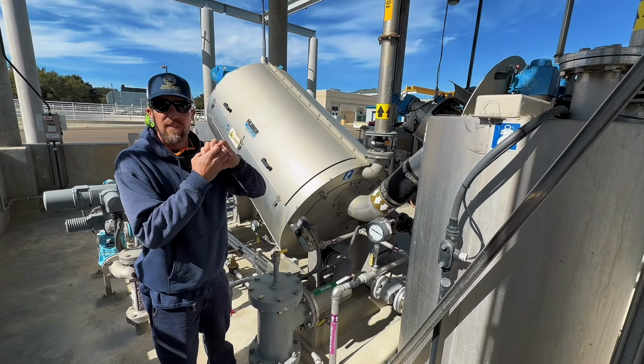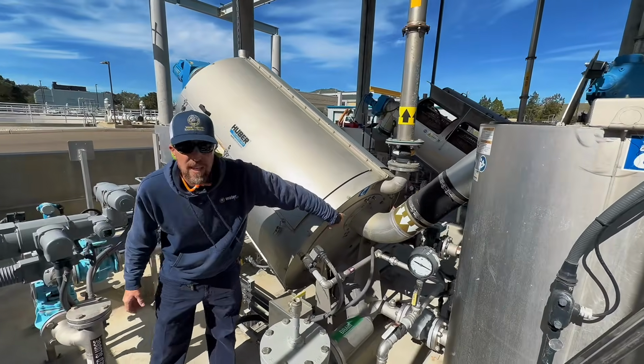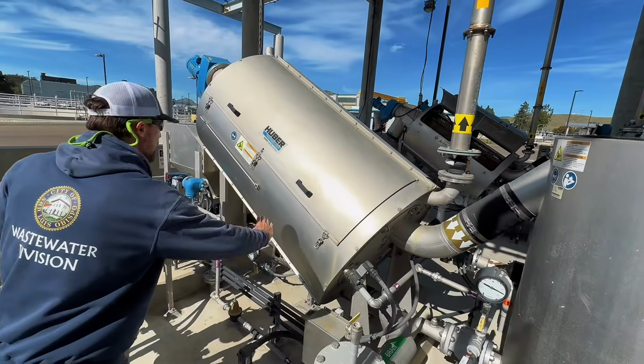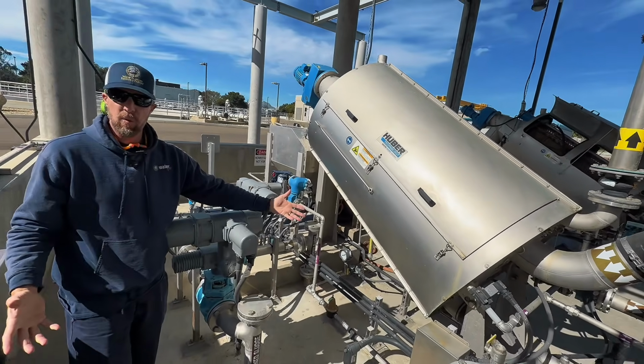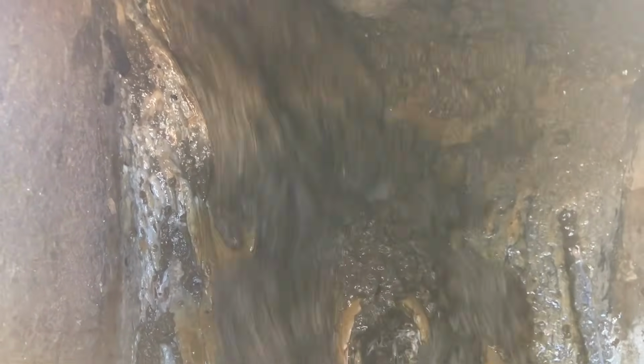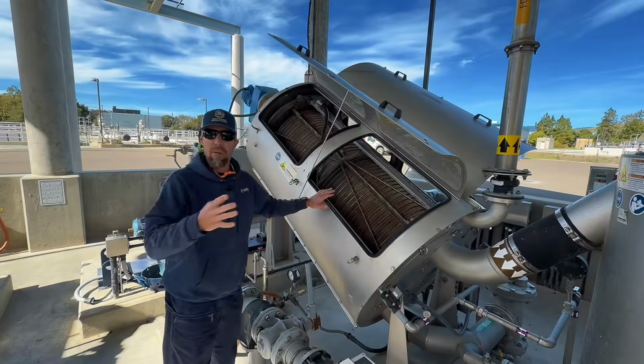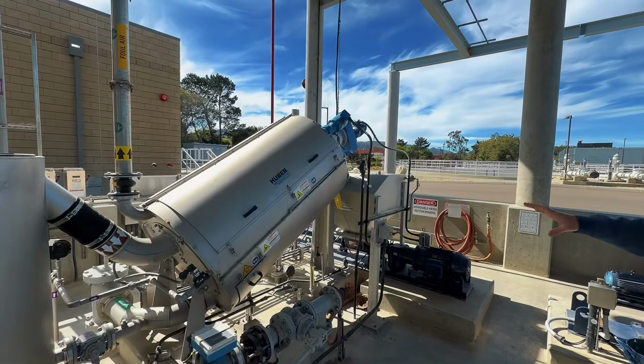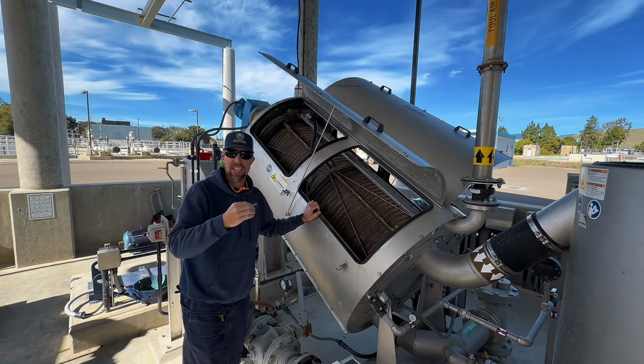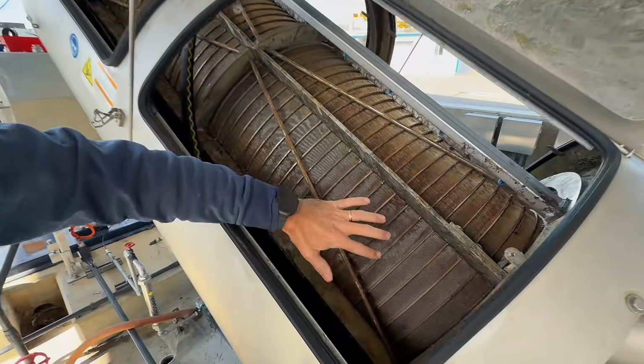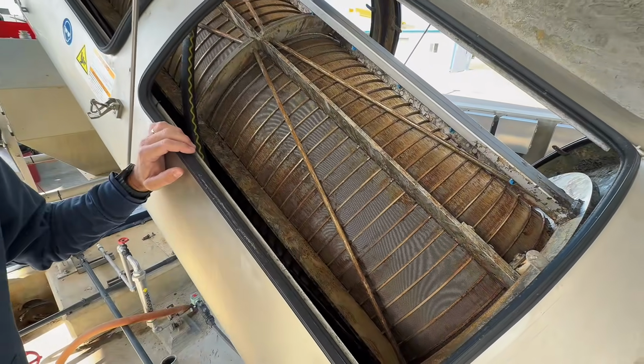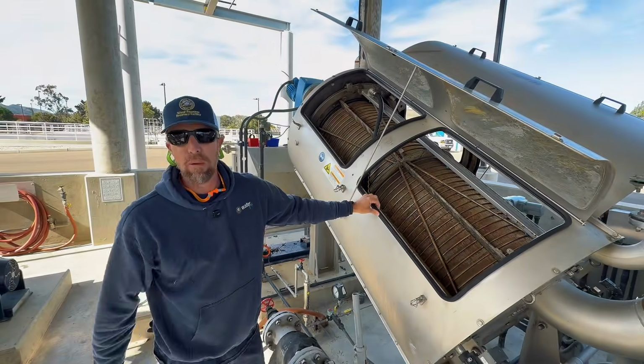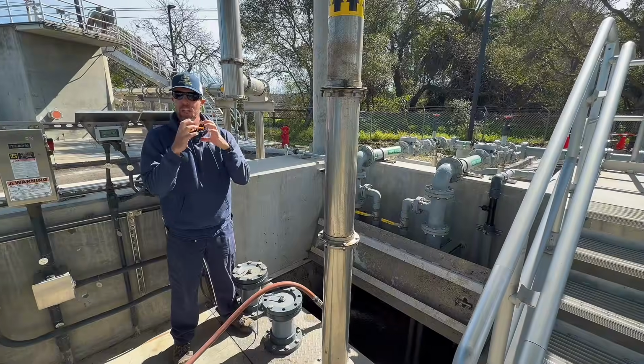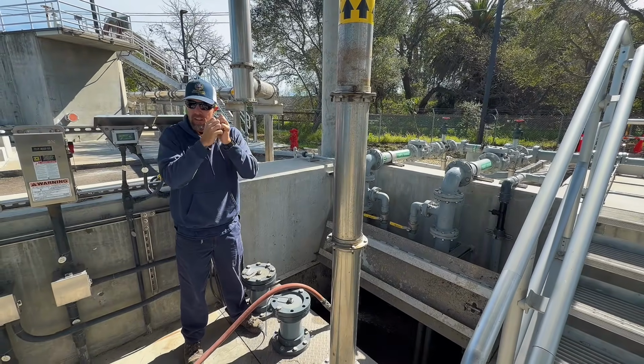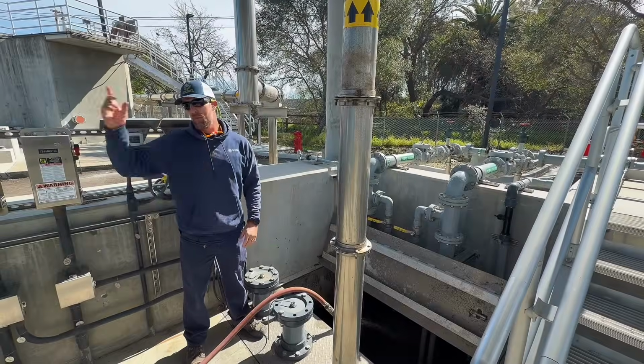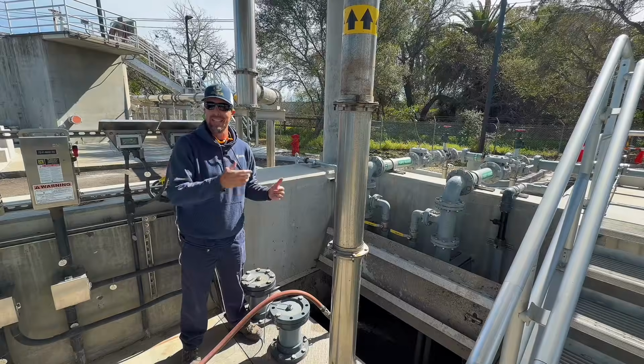So these clumps or flocs of solids feed into the drum thickener right here. You see how it's on an angle — going up, so all the water falls away, and all the solids are conveyed up and into the thickened sludge hopper. Back to redundancy — sometimes things go wrong, this one's online, this one's not, which affords you a chance to see what the insides look like. This mesh holds the solids in, and the water is allowed to leave and be pumped to the front of the plant. This is the filtrate — all those solids are kept within the drum and pumped to anaerobic digestion, while the water that escapes is pumped back to the front of the plant, back to headworks for treatment in the liquids treatment train.